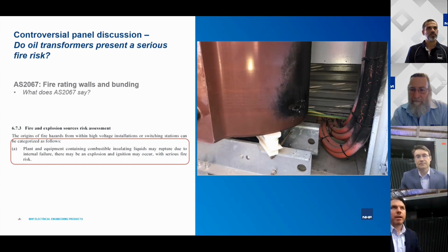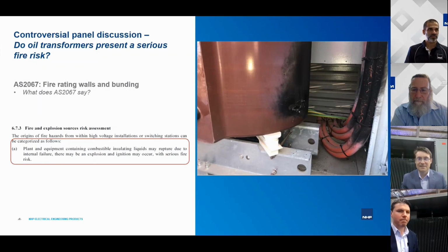Interesting point. The thing we did bring up previously is we said the oil transformer was bulletproof, though. So, in the event, I think you've got a saying, with oil transformers the chances of it going wrong are very, very low. But when they do go wrong, it could be quite significant in that case, can't it? Yeah, exactly. Low probability but high consequences. There we go. That's a better way to put it.